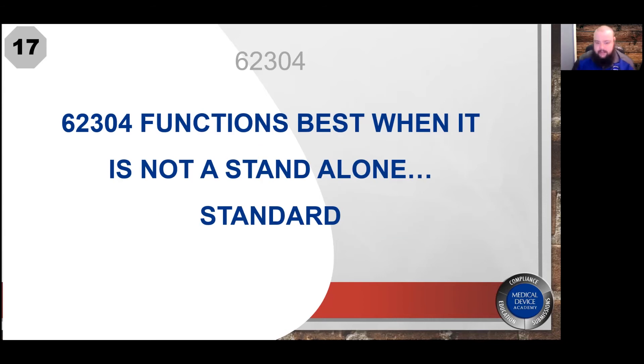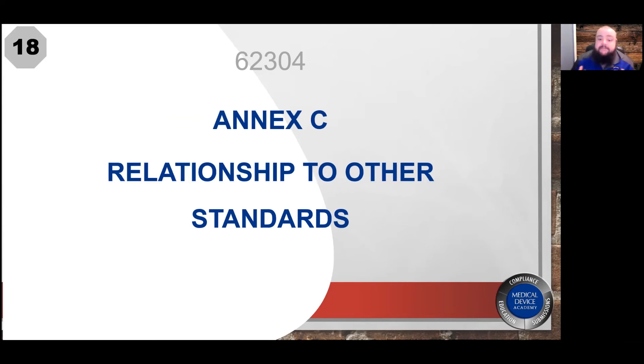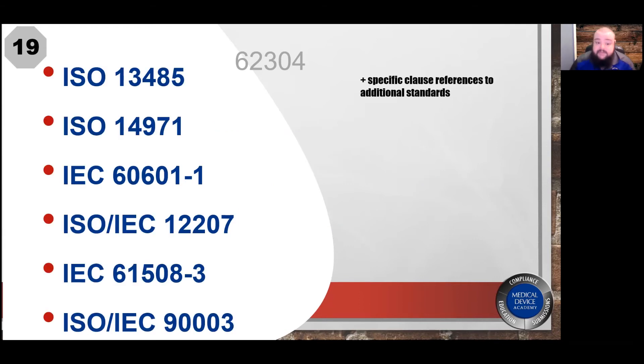Just like many other international standards, 62304 functions best when it's not used as a standalone standard. In fact, there's a dedicated annex that explains the relationship of 62304 to other international standards. Specifically, those standards happen to be 13485, 14971, 60601-1, 12207, 61508-3, and 90003. That doesn't mean those are the only standards referenced — reading through 62304, it will contain specific references to individual clauses of other standards, called out within the text of 62304.